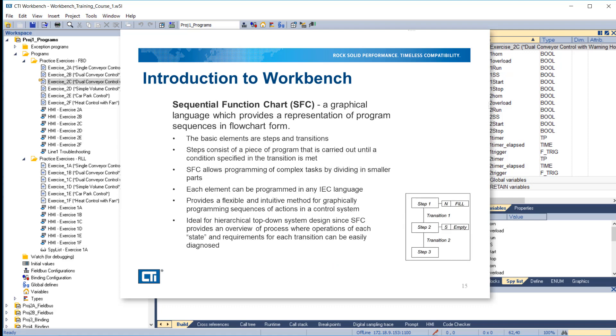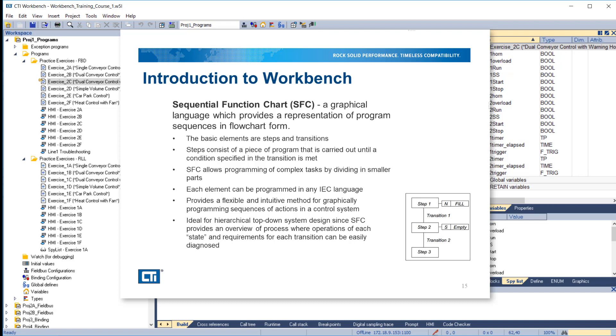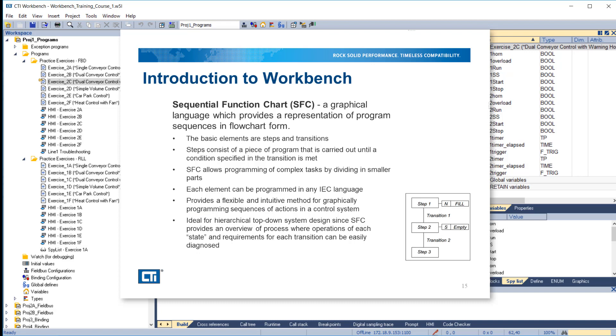Sequential function chart is a graphical language which provides a representation of program sequences in flowchart form. The basic elements of SFC are steps and transitions. Steps consist of a piece of program that is carried out until the condition specified in the transition is met. SFC allows programming of complex tasks by dividing them into smaller parts. Each element can be programmed in any IEC language. SFC provides a flexible and intuitive method for graphically programming sequences of actions in a control system. It is ideal for hierarchical top-down system design, since SFC provides an overview of the process where operations of each state and requirements for each transition can be easily diagnosed.